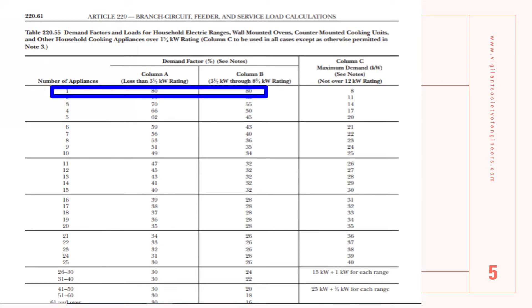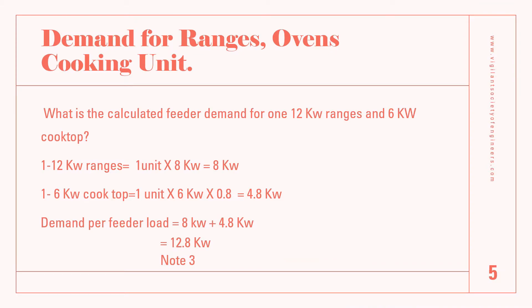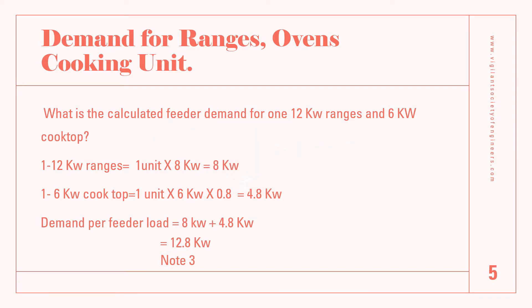From column B, the demand factor is 0.8, or 80 percent. So that value for the 6 kilowatt cooktop is 4.8 kilowatt. The total demand for this feeder supplying one 12 kilowatt range and one 6 kilowatt cooktop is found by adding both demand values: 8 kilowatt plus 4.8 kilowatt, resulting in a total demand of 12.8 kilowatt.